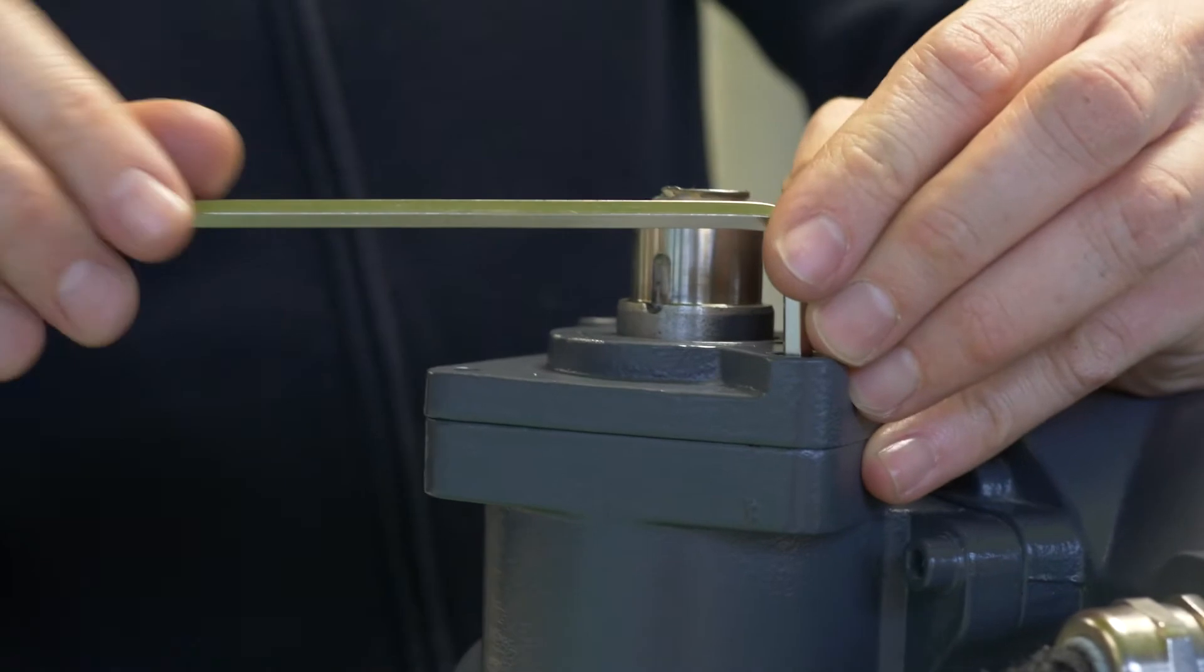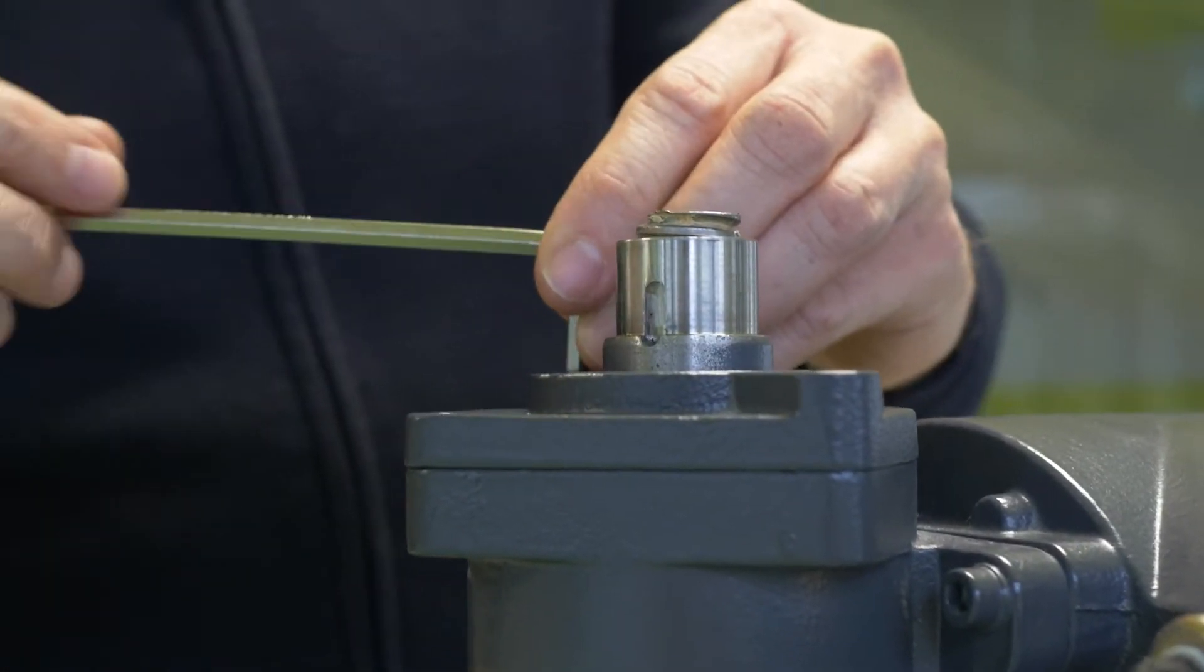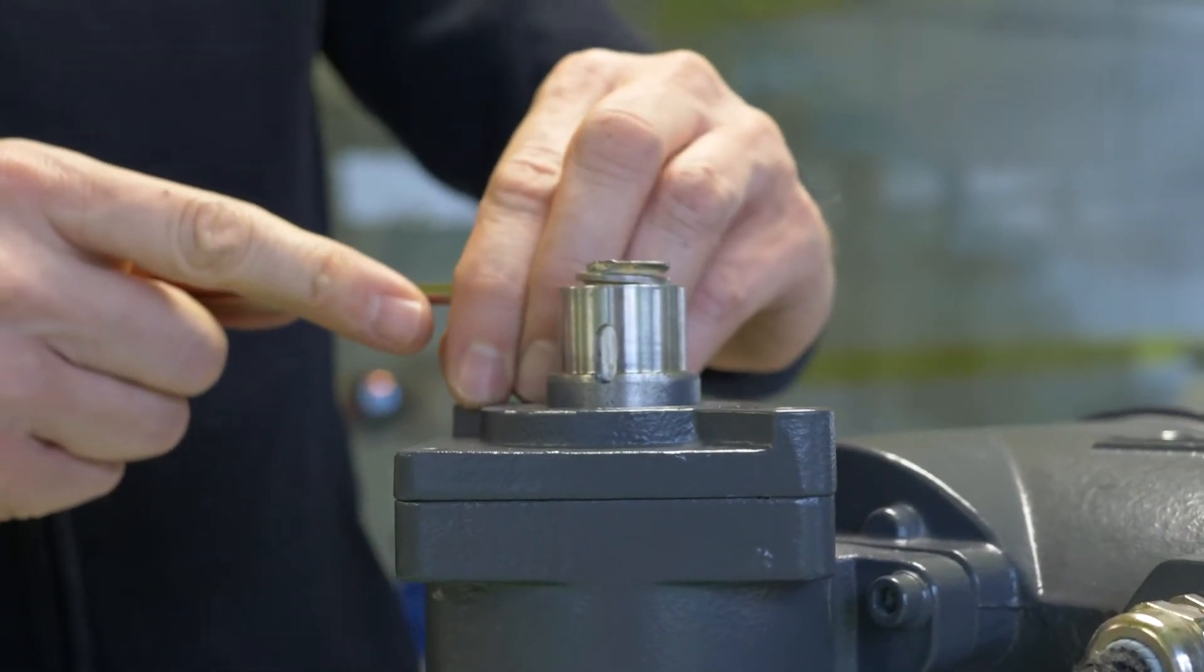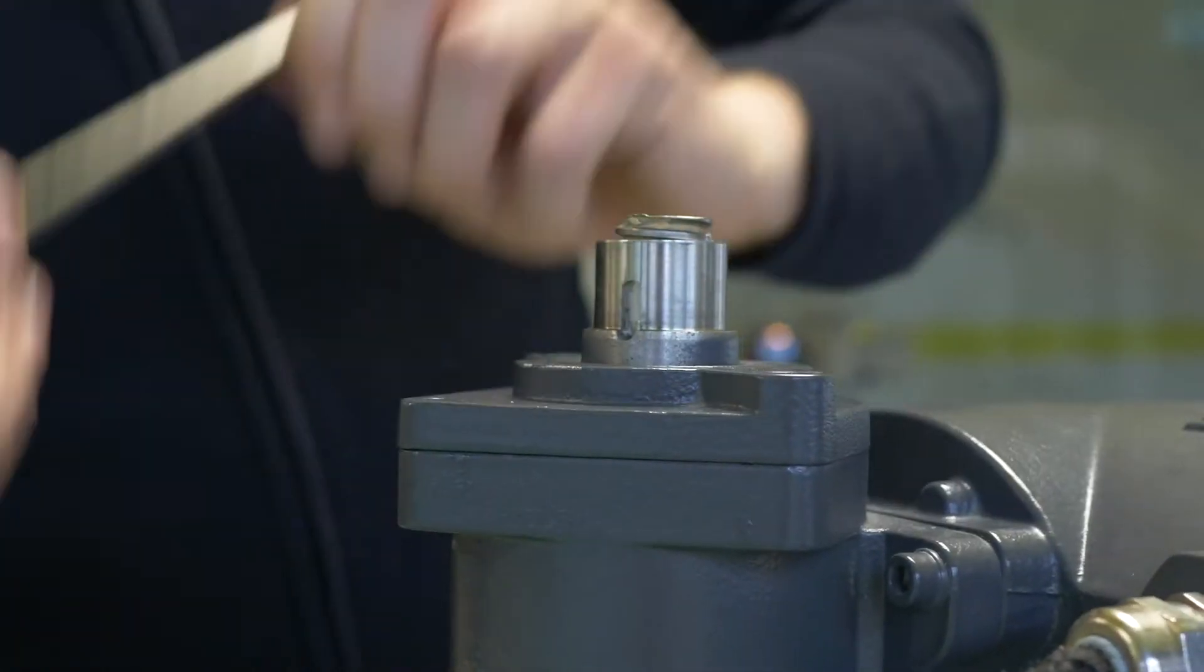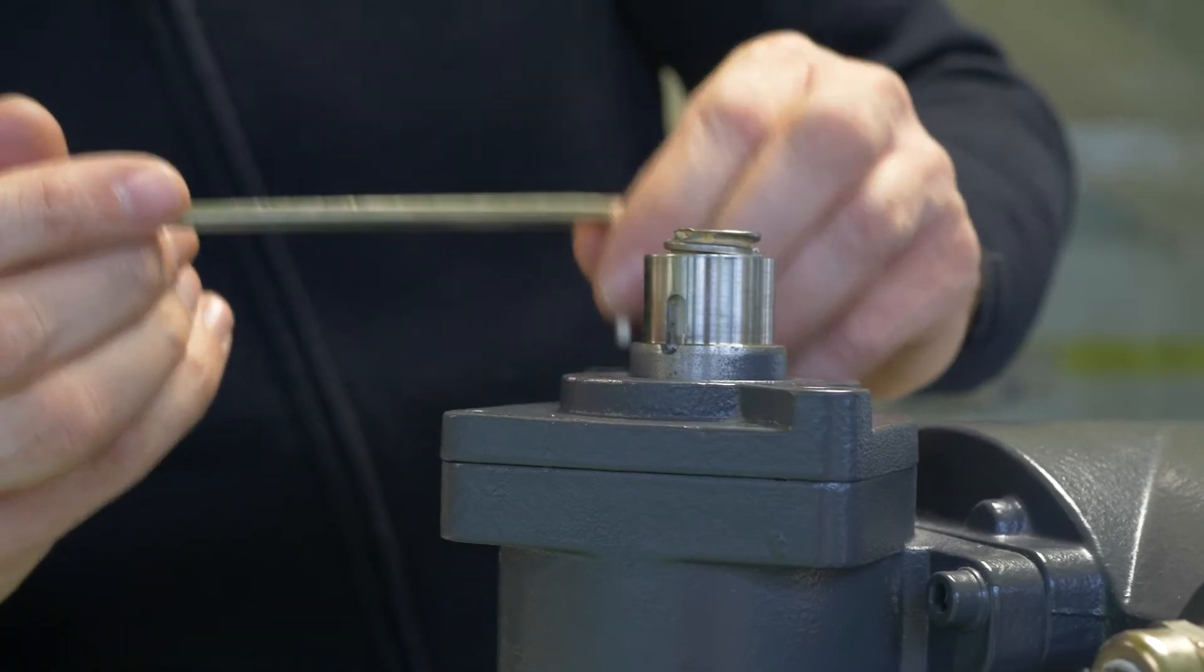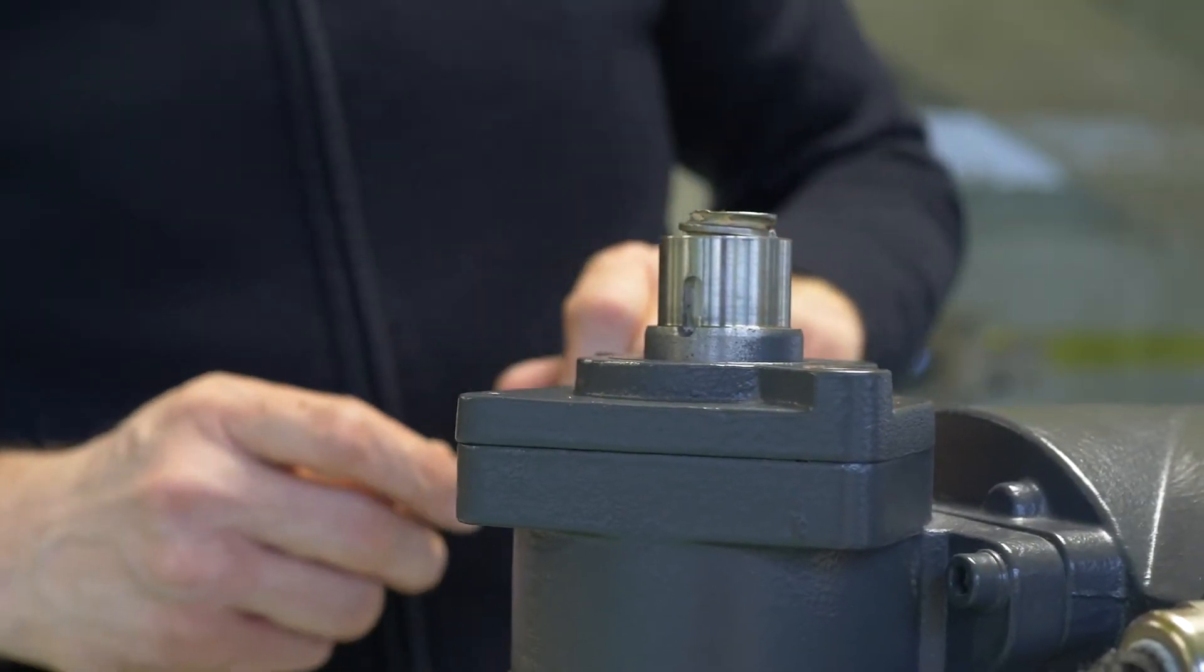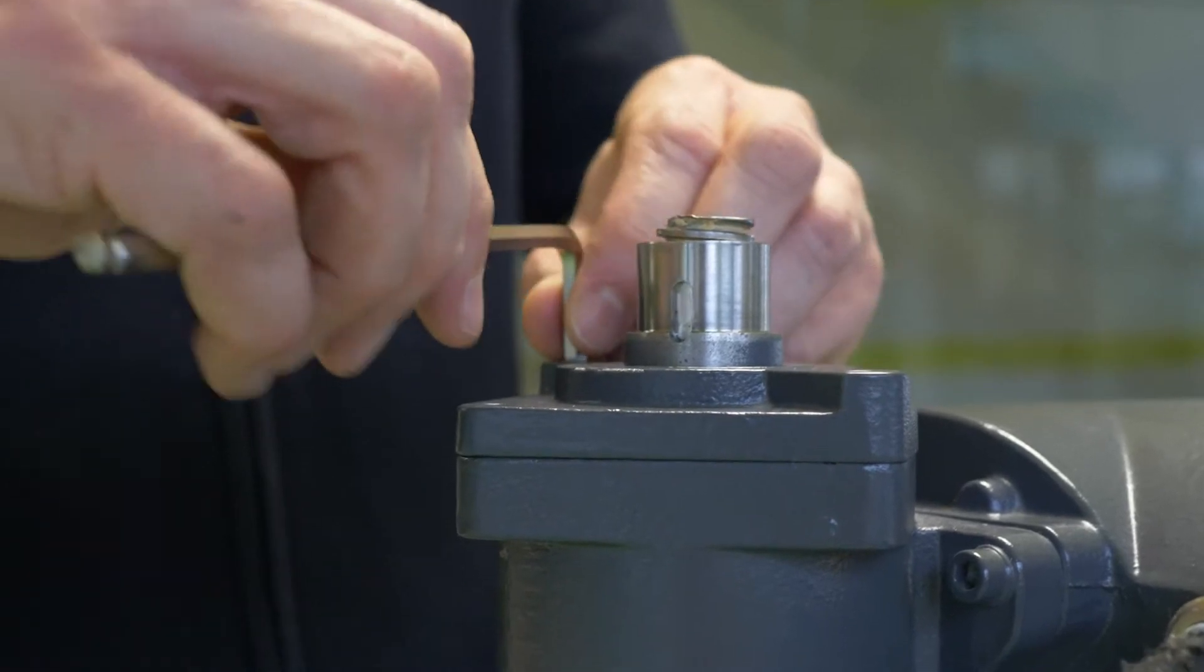You should be careful to tighten it not too strong because we have here an aluminum housing and it could happen that you damage the thread in the housing. When this happens you have to change the complete actuator housing and this is not so funny.